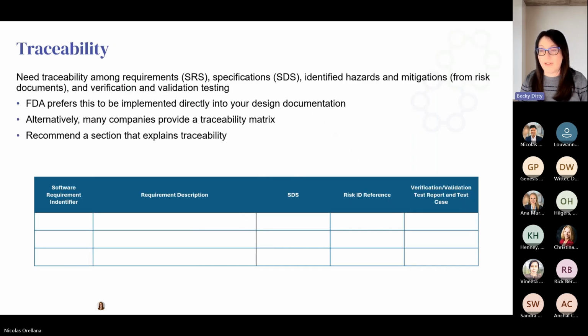What you'll also need to provide to FDA is traceability from your requirements to your design, to your risks, and to your testing. Historically, people have done a traceability matrix, which may look something like what's on the screen below, where you have a line item for every software requirement. And then you identify where the design details about that requirement are. What's the SDS document? What's the section of the SDS? Any risk IDs that software requirement may be mitigating. And then finally, what's the test report and the test case that verifies that software requirement? So that's historically how traceability has been done.